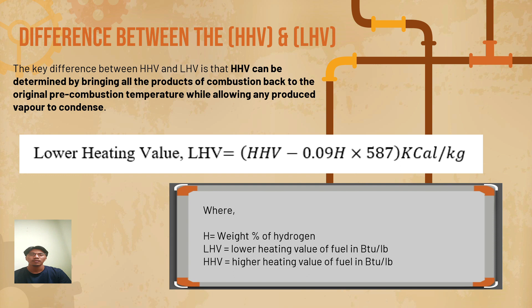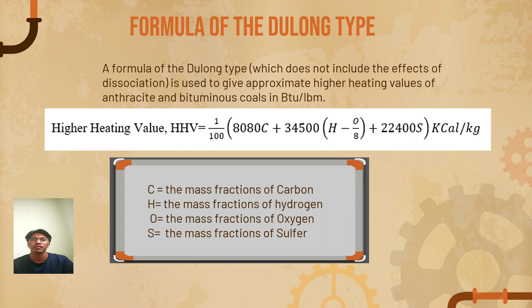The formula of Dulong type. Dulong type is a formula that is used to give approximate higher heating value of anthracite and bituminous coal, which does not include the effect of dissociation. So the formula is higher heating value equals 1/100 times 8080 times the mass fraction of carbon plus 34,500 times the mass fraction of hydrogen minus the mass fraction of oxygen over 8, plus 22,400 times the mass fraction of sulfur.